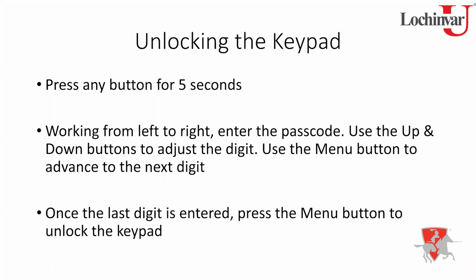Again, your passcode screen is going to come up. Again, working from left to right, now you've got to enter the passcode. Once that last digit's in, you press the menu button. Then, if you've put it in correctly, it's going to flash unlock keypad or keypad unlocked at this point. Now you can make your adjustments. Key thing is, if somebody does this, make sure you write that number down, right? Absolutely. Make sure you write that number down. So keep that in mind. All right. Most people typically don't, but it is there.